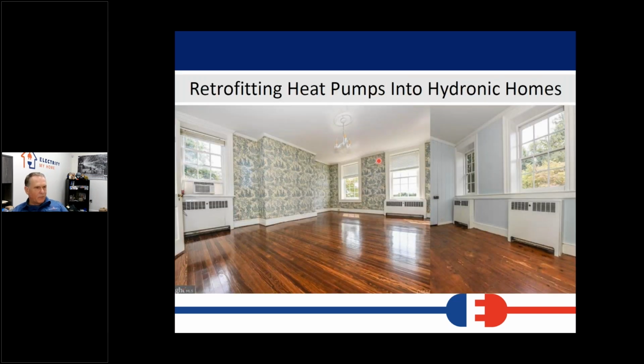And this is happening a lot more as well. Retrofitting heat pumps into hydronic homes. We just looked at a project on this a couple of weeks ago that I happily handed off to a very, very good plumber. But old boilers typically run, the one we were looking at the other day was 113,000 BTUs, and we really don't have heat pumps that operate at that BTU range. So the strategy was to use a very large storage tank, keep that up to temperature so that it could saturate the hydronic fields in the house.